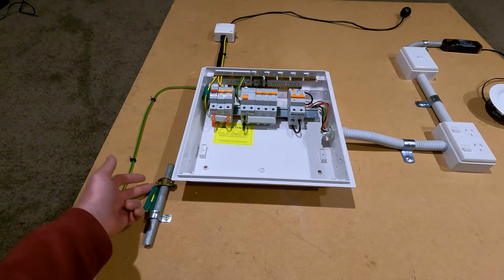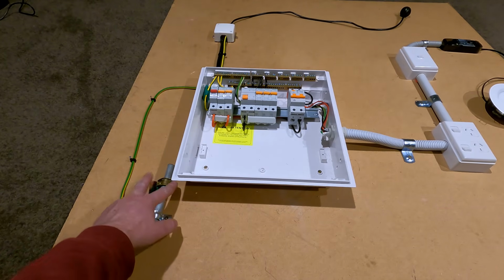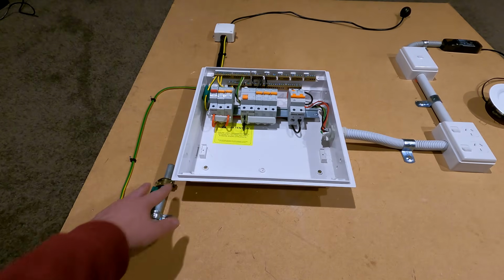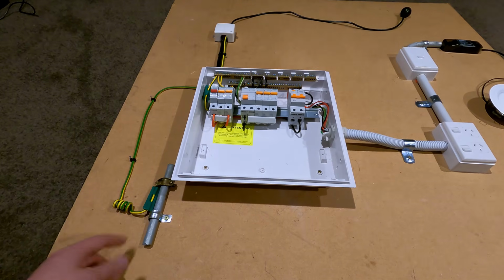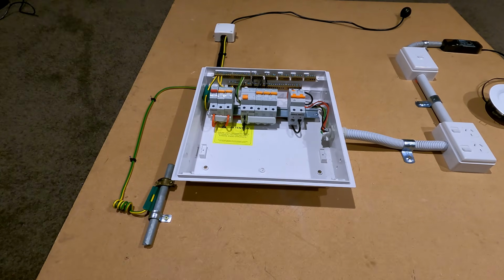So you might want to check between both sides of the clamp to make sure there's minimal resistance between them, and make sure that you haven't clamped onto the insulation of the cable instead of the copper conductors. Moving on. So the next test in the sequence of tests is doing your equipotential bonding. Along with equipotential bonding is also the other earthing conductors.